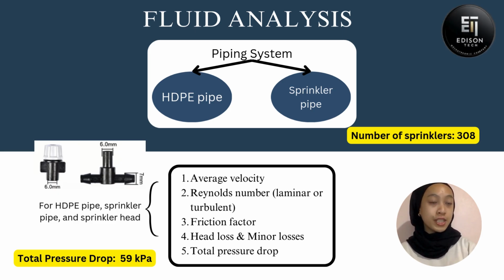Moving on to the calculation, the parameters that we calculate for the pipes and also the sprinkler head are the average velocity, the Reynolds number to see whether the flow is laminar or turbulent, the friction factor, the head loss and minor losses, and also the total pressure drop. After doing our calculation, we have found that the total pressure drop for our system is 59 kilopascal.